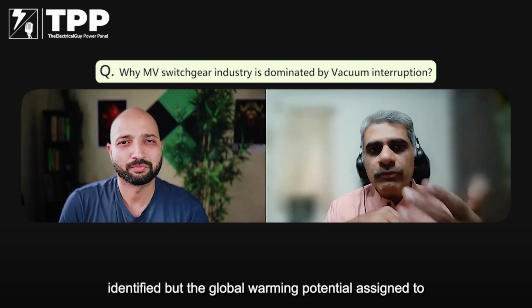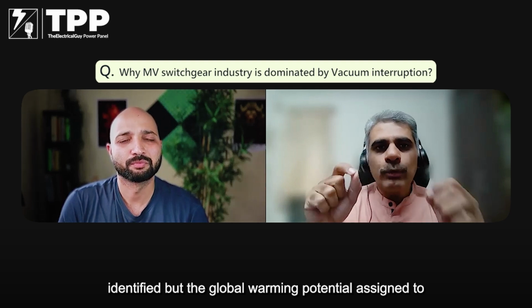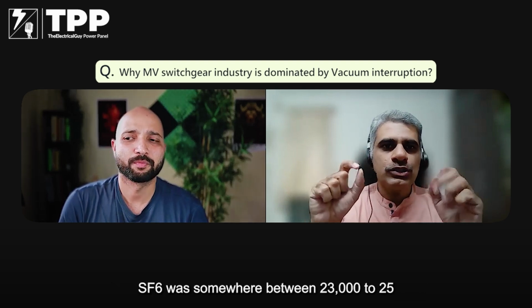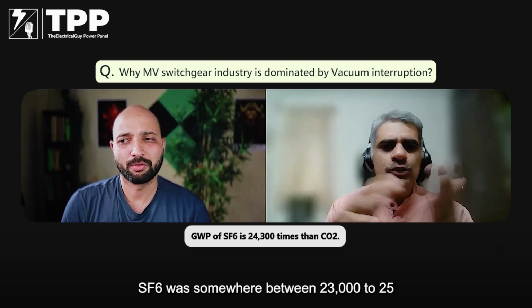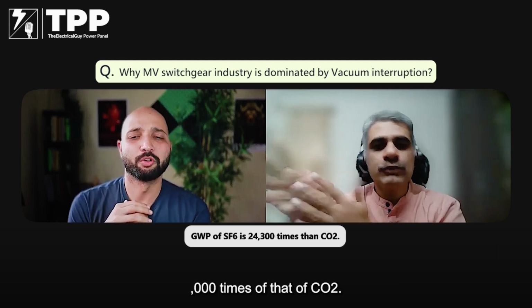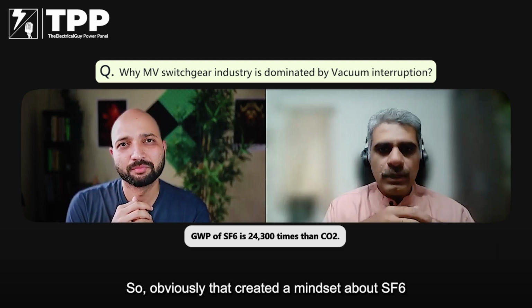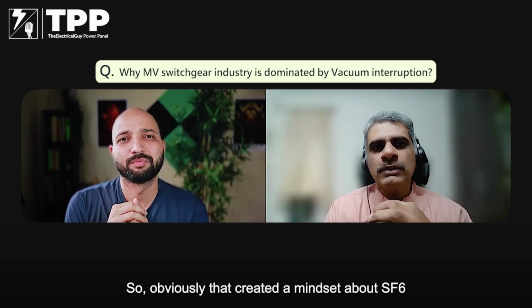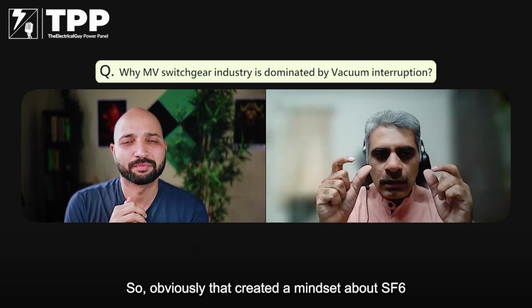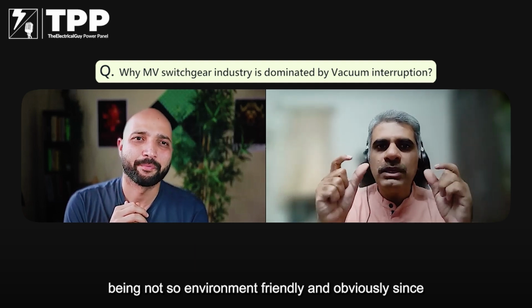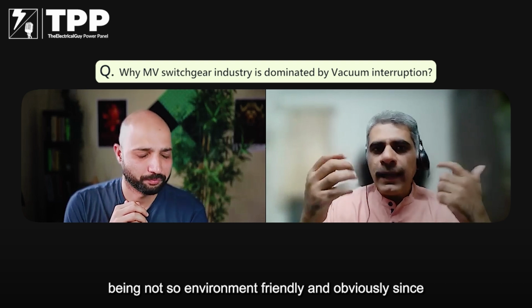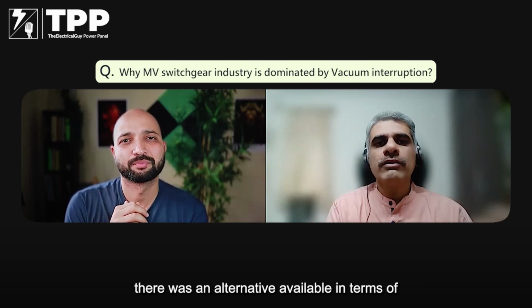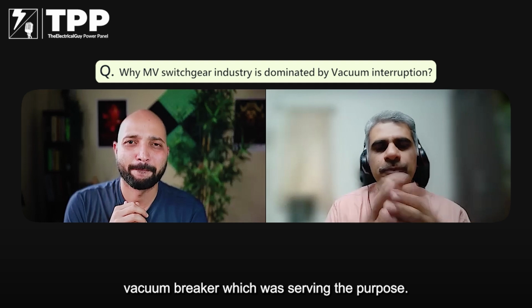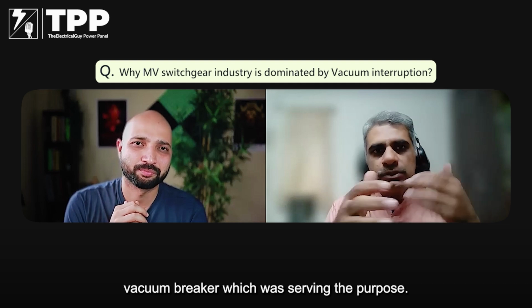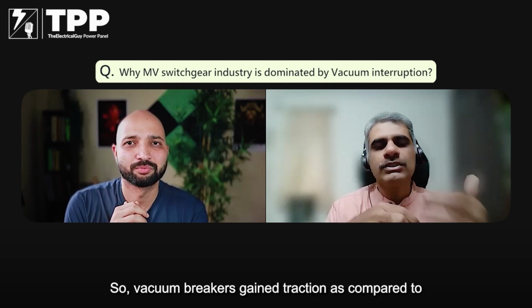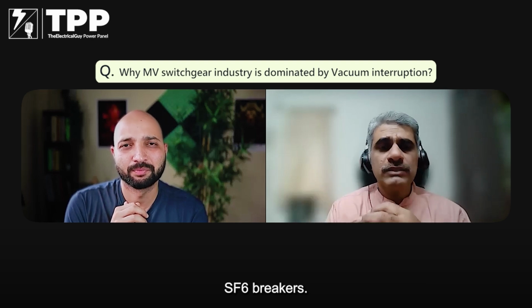And not just identified, but the global warming potential assigned to SF6 was somewhere between 23,000 to 25,000 times that of CO2. So it's huge. So obviously, that created a mindset about SF6 being not so environment friendly. And obviously, since there was an alternative available in terms of vacuum breaker, which was serving the purpose, vacuum breakers gained traction as compared to SF6 breakers.